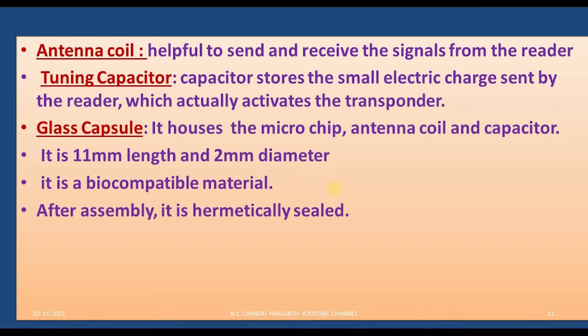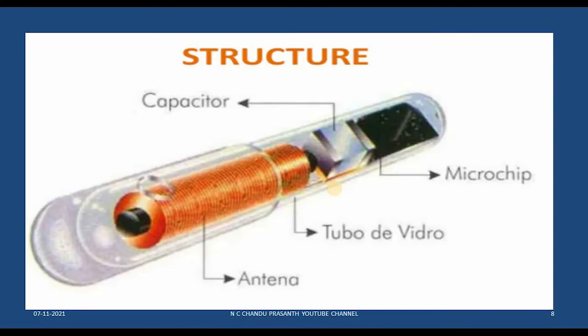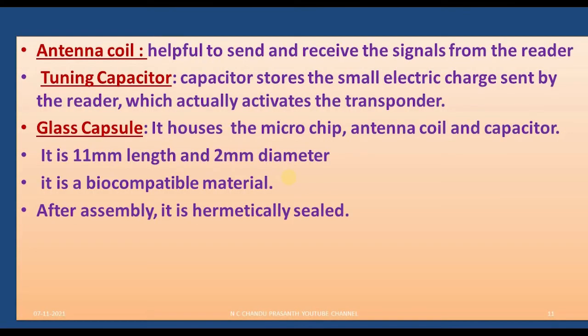The glass capsule holds all the different components — the microchip, antenna coil, and capacitor. It is 11 millimeters in length and 2 millimeters in diameter. It is made of biocompatible material, and after assembly it is hermetically sealed — an airtight glass capsule.